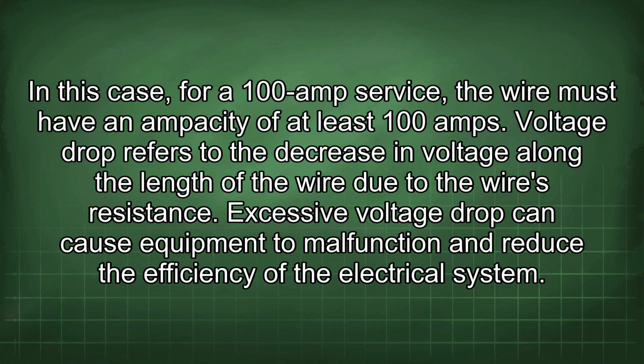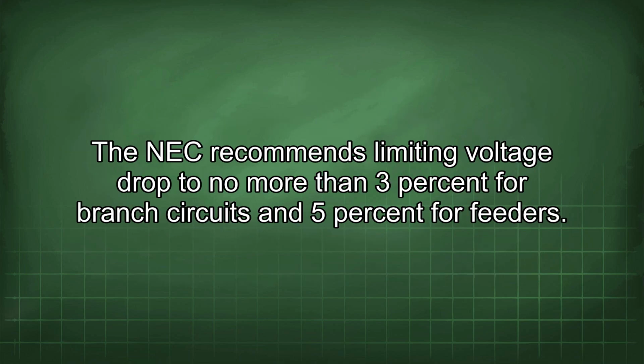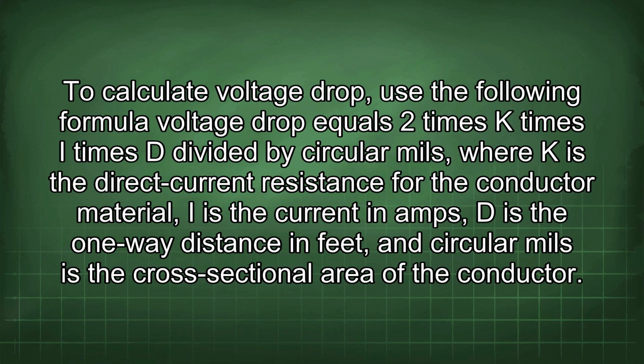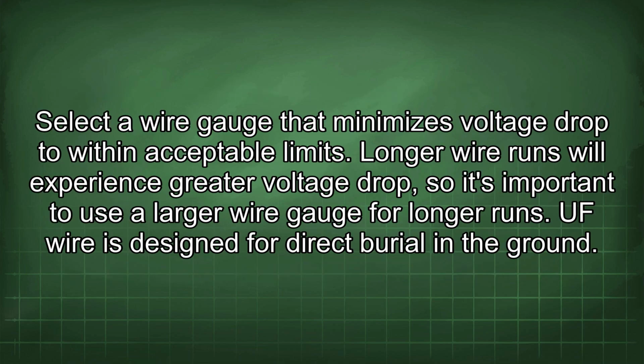Voltage drop refers to the decrease in voltage along the length of the wire due to the wire's resistance. Excessive voltage drop can cause equipment to malfunction and reduce the efficiency of the electrical system. The NEC recommends limiting voltage drop to no more than 3% for branch circuits and 5% for feeders. To calculate voltage drop, use the following formula: voltage drop equals 2 times K times I times D divided by circular mils, where K is the direct current resistance for the conductor material, I is the current in amps, D is the one-way distance in feet, and circular mils is the cross-sectional area of the conductor. Select a wire gauge that minimizes voltage drop to within acceptable limits. Longer wire runs will experience greater voltage drop, so it's important to use a larger wire gauge for longer runs.